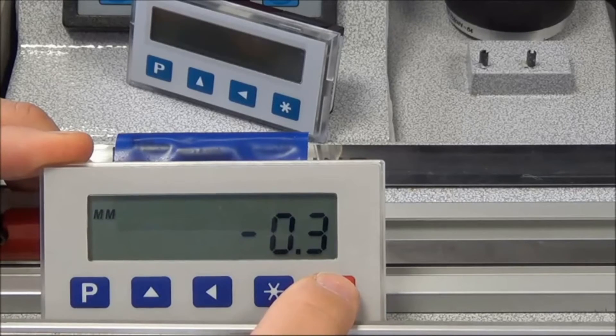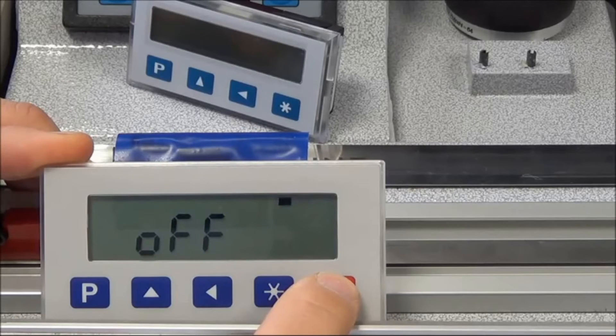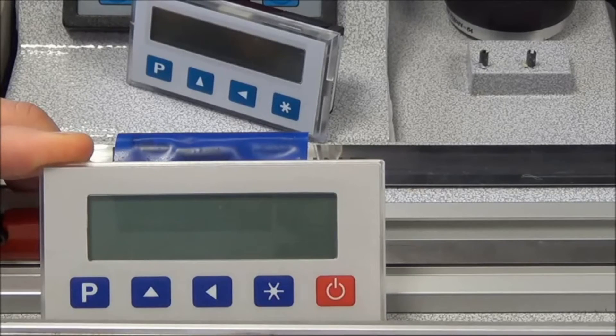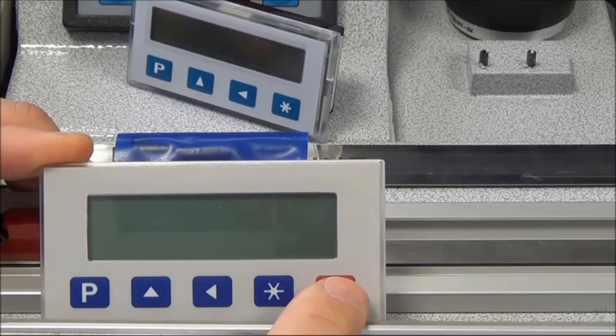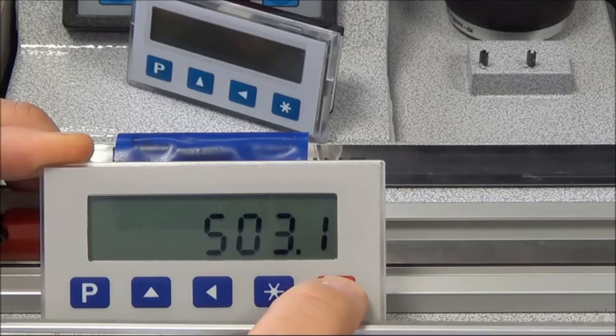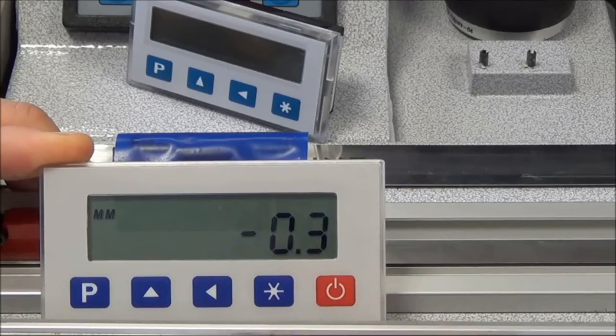Then we can switch the axis off. We know that the customer hasn't moved the axis with the power off, so we should still be at -0.3. We switch it on and it's -0.3, so the axis hasn't moved and the display isn't flashing to indicate that we need to datum the axis.